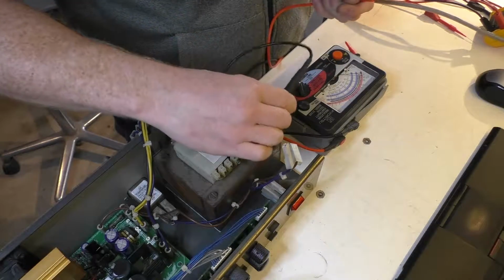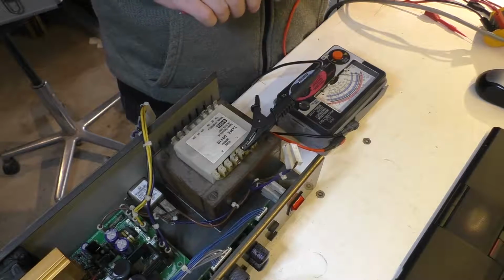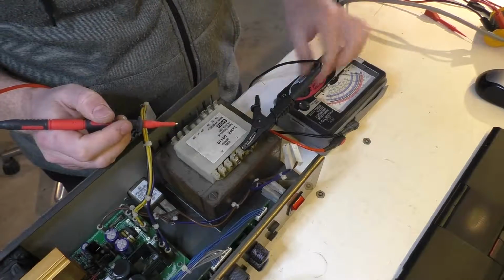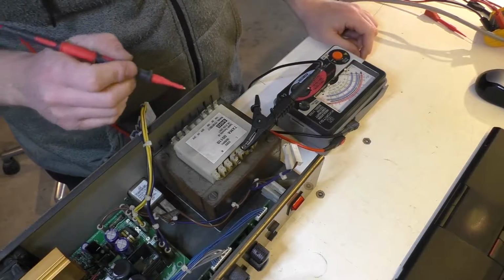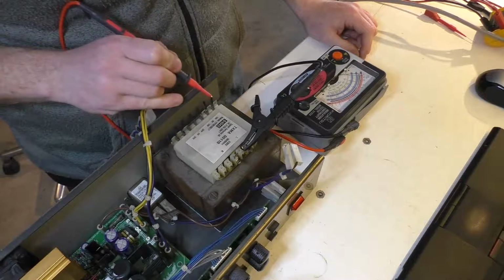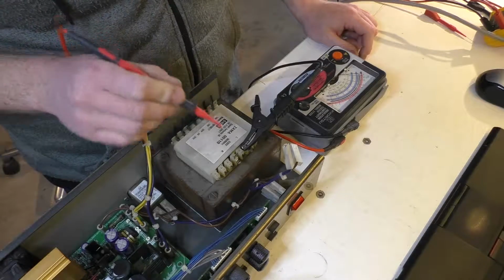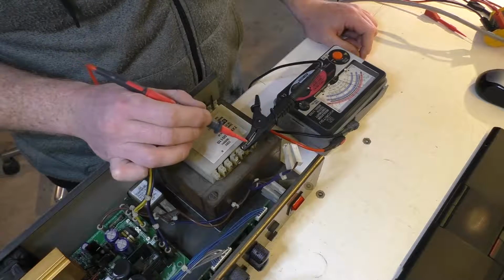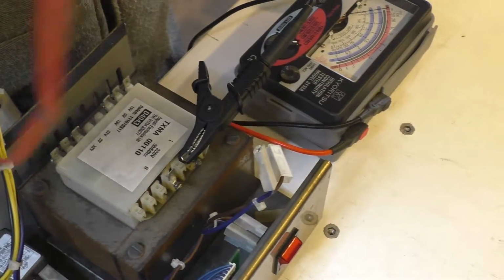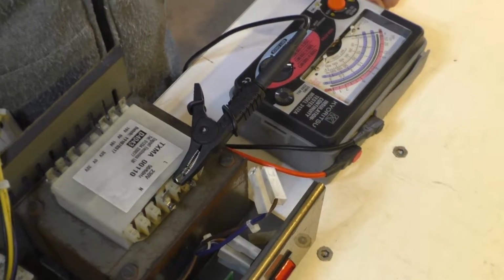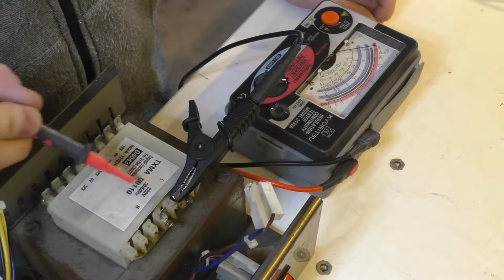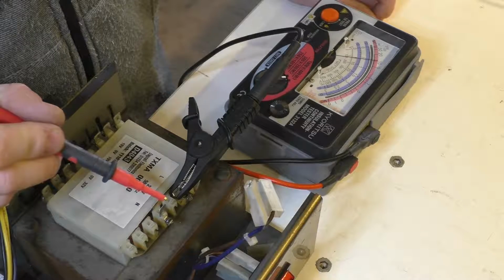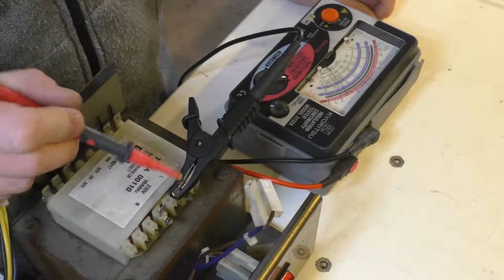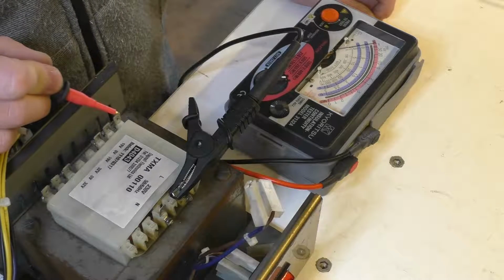And you can see if there's leakage from winding to winding. It doesn't show you shorted turns, but it'll show you if it's melted through the insulation between two layers of winding. So click it up to 1,000 volts, push it in. So that's showing no leakage there. If I touch there, see it goes through the roof. Might zoom in a bit there. Alright, so because that winding goes between there, if I touch there, it's showing that there's a dead short there. If I go there, showing nothing, which is what you want.